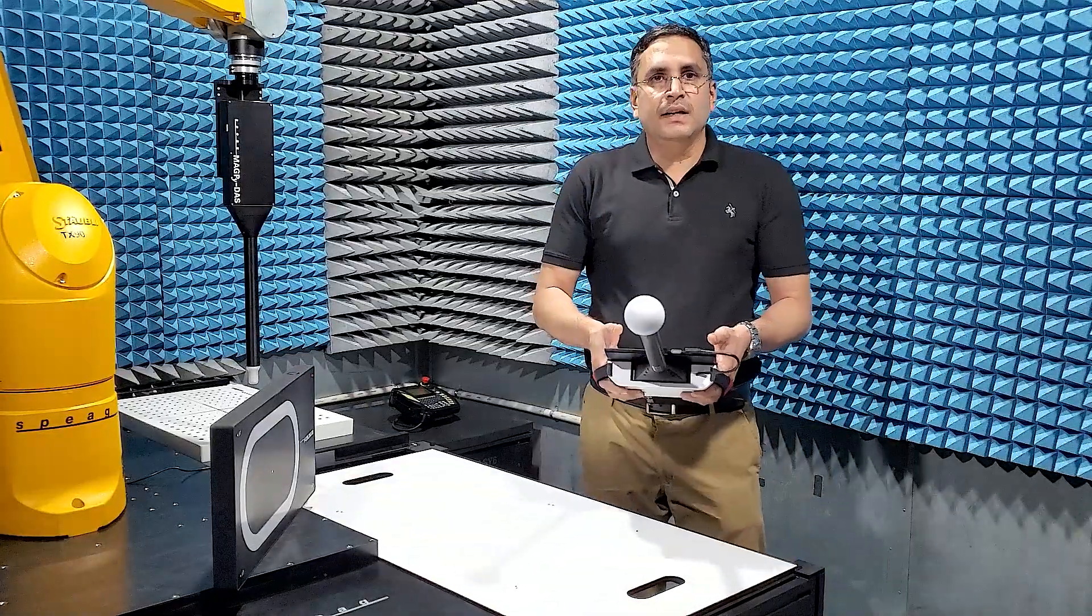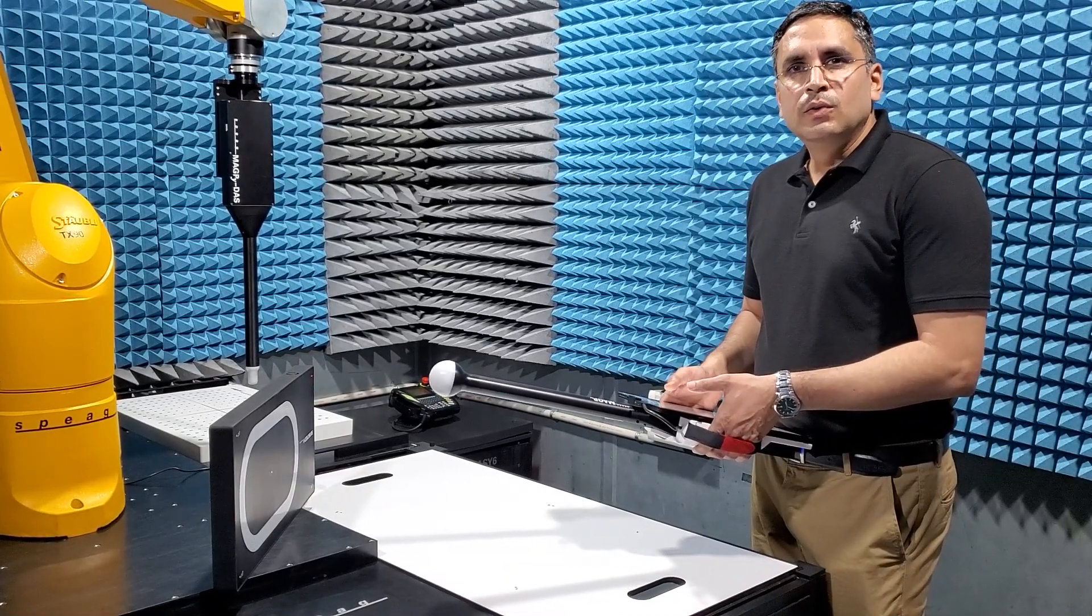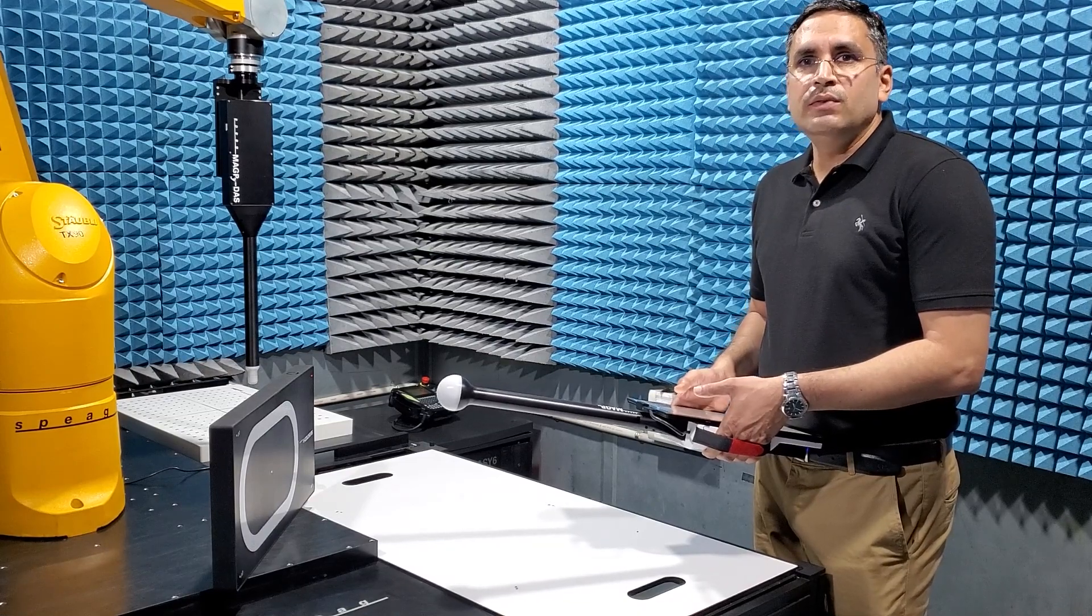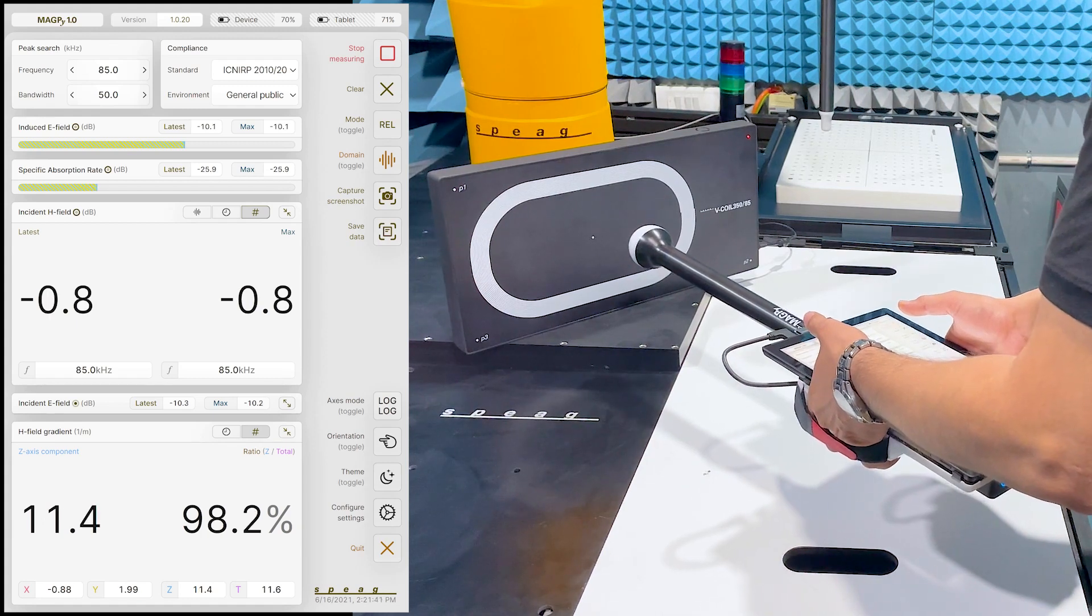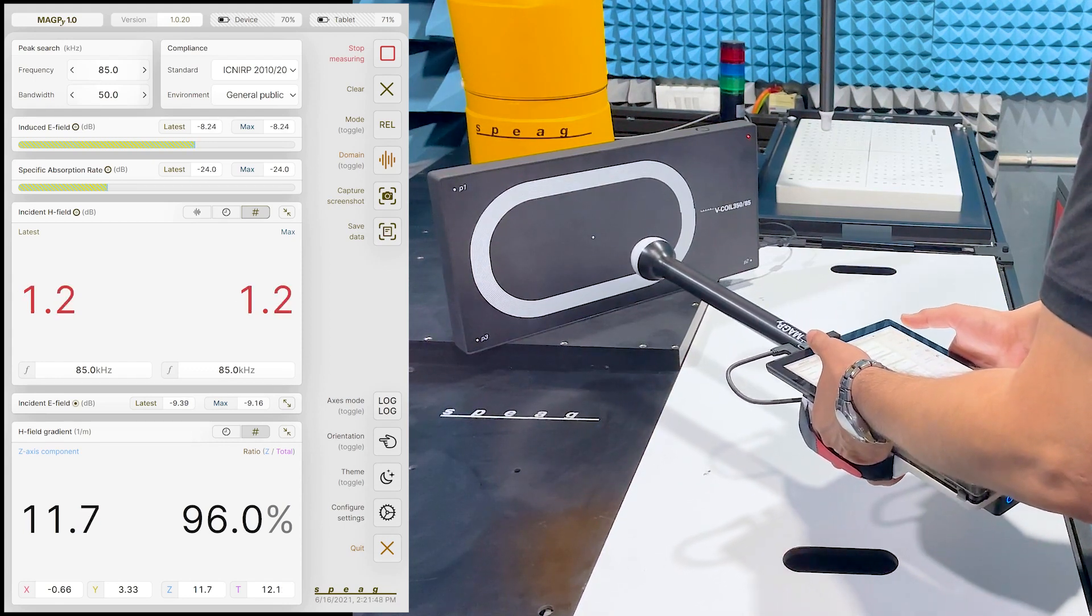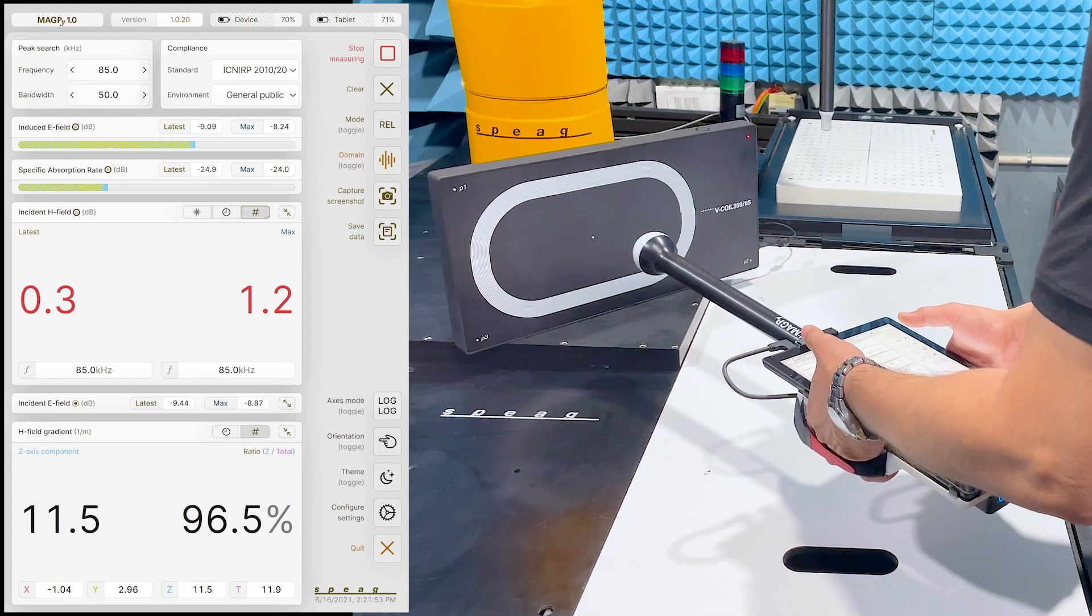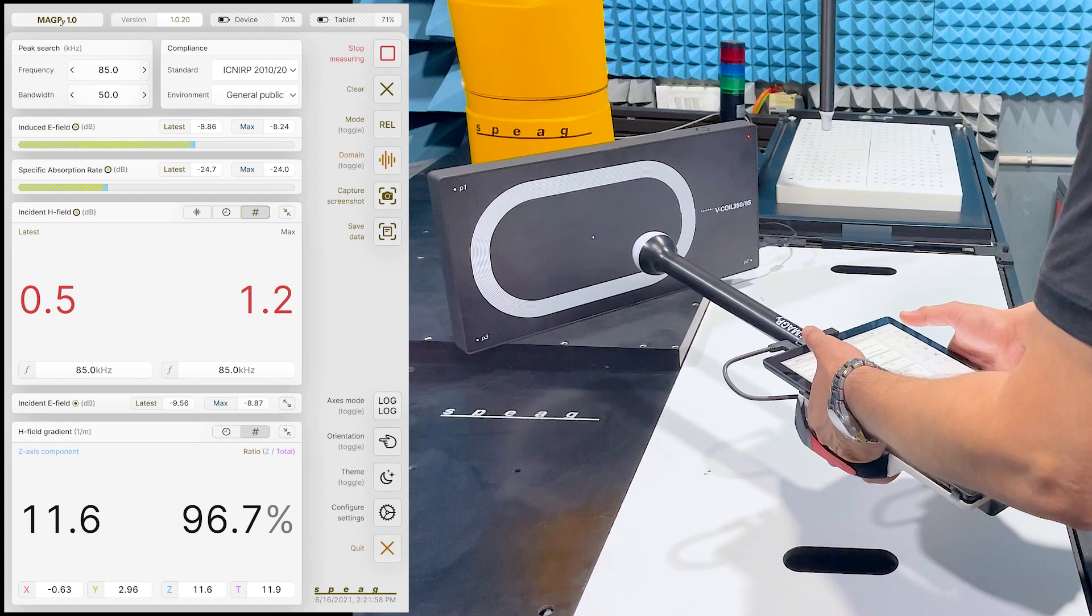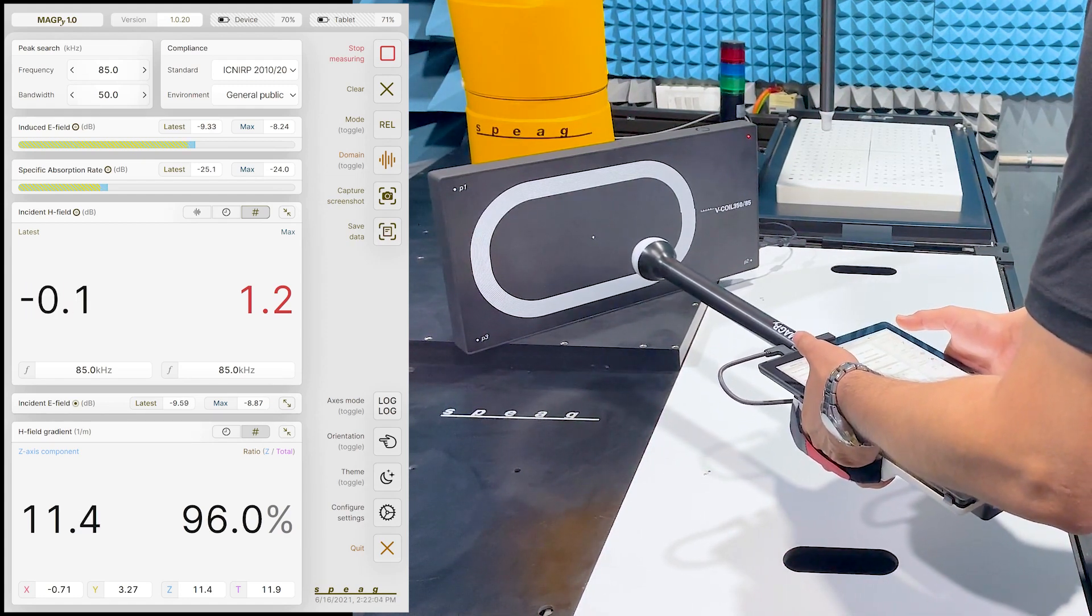First, I select the settings. Next, we move the device slowly towards the center of the coil and observe the latest relative incident H field value. So, at this point, the relative incident H field value in dB begins to turn positive. Which means this is the boundary for incident H field and is approximately 15 cm from the tip of the probe to the source. So, this would be the compliance boundary for conventional evaluations.